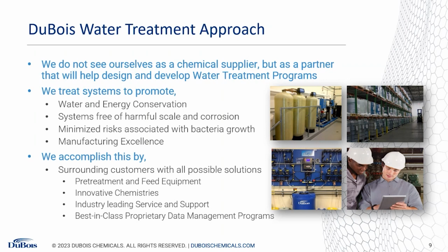Now we can run products to the ragged edge to really maximize water savings, because if something goes wrong, we know instantly. If a bleed valve gets stuck open, you'll know within minutes. If a chemical pump loses prime, a flow meter can tell us that no product's flowing through it. If water savings aren't what we're expecting, we'll see that in water meter readings. So we can always evaluate our systems and see how you're doing and really provide service wherever we are, 24/7.